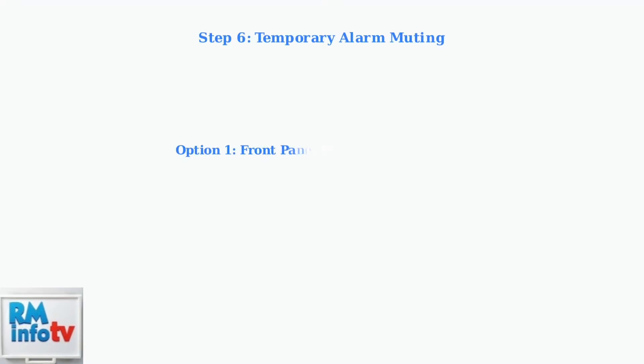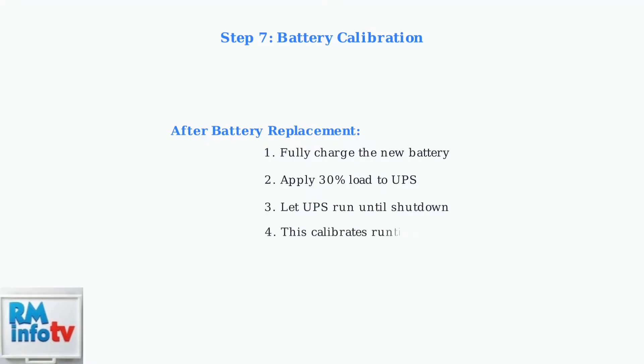As a temporary measure, you can mute the alarm via the front panel menu or through APC software like PowerChute Personal Edition. After replacing the battery, calibrate the UPS by fully charging it, then applying a 30% load until the UPS shuts down. This ensures accurate runtime readings.